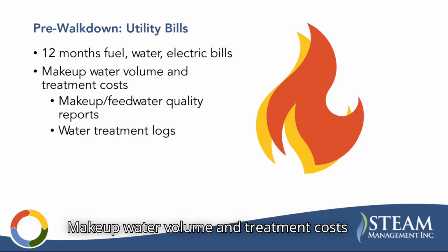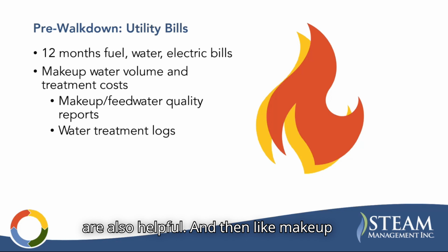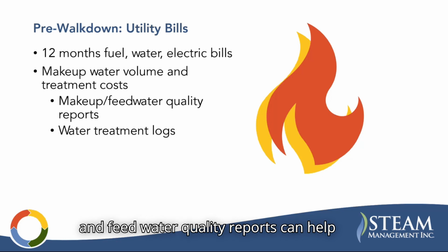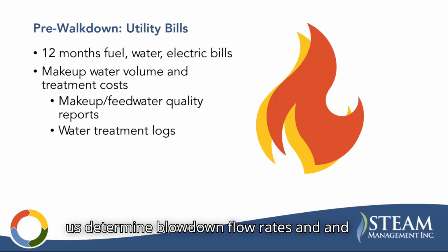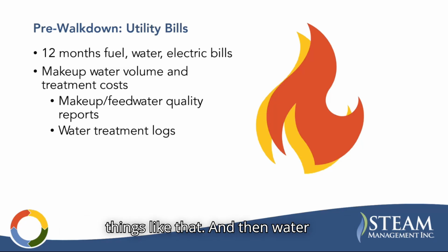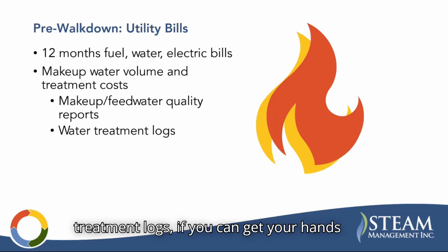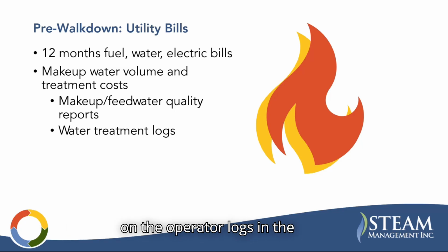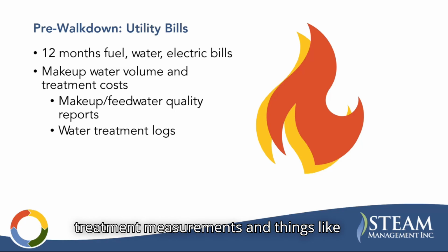Makeup water volume and treatment costs are also helpful. And then makeup and feed water quality reports can help us determine blowdown flow rates and things like that. And then water treatment logs, like if you can get your hands on the operator logs in the boiler room that show water treatment measurements and things like that.